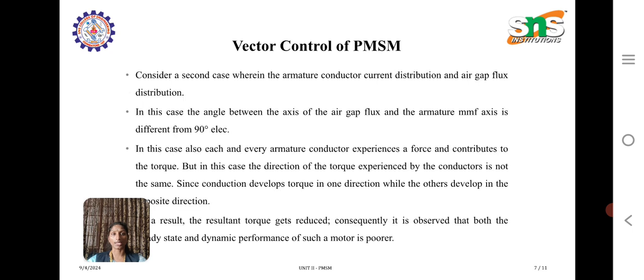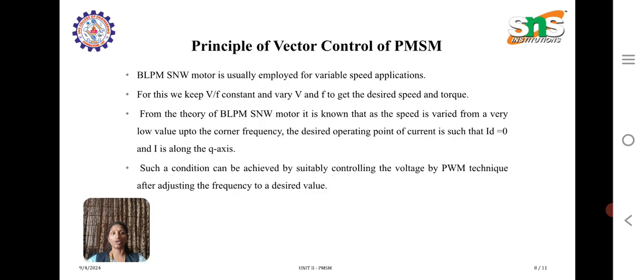Coming to vector control in detail, we consider two parameters: voltage and frequency. We call this V by F control. For this, we keep V by F constant, and we can vary V and F to get the desired speed and torque. From the theory of brushless permanent magnet sine wave motor, it is known that as speed is varied from a very low value up to the corner frequency, the desired operating point of current is such that Id will be equal to zero and that current is along the q-axis, the quadrature axis. Such a condition can be achieved by suitably controlling voltage by PWM technique after adjusting frequency to a desired value. From here we observe that by varying voltage and frequency, the desired speed can be achieved using vector control technique.